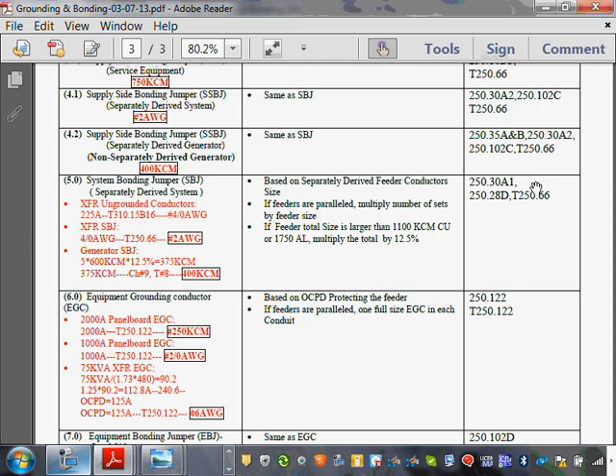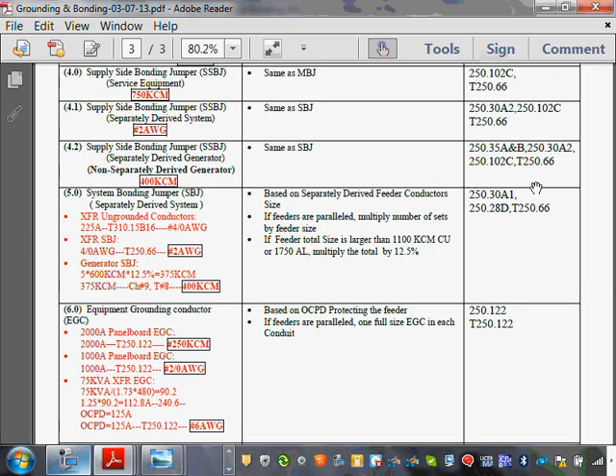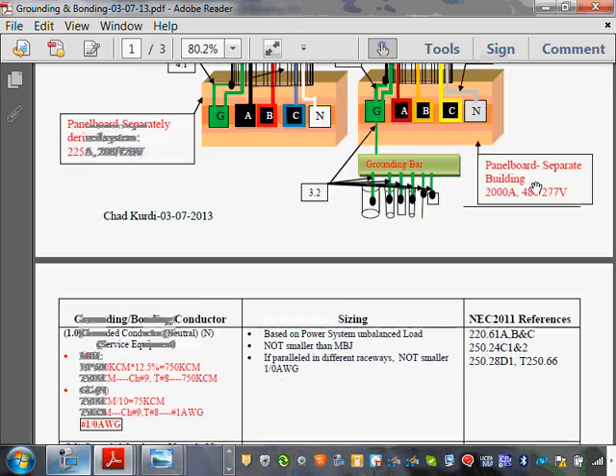Now the exception, there's always exceptions. If you parallel, if you have multiple conduits coming into that transformer, then you have 2 options. Either daisy chain all of them, same as the system bonding jumper, or home run from each conduit. Now it becomes slightly different. Home run from each conduit, but it still cannot be sized the same way as with the home runs. So that's the supply side bonding jumper.